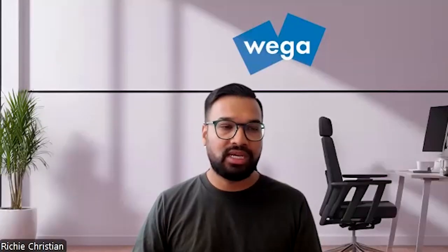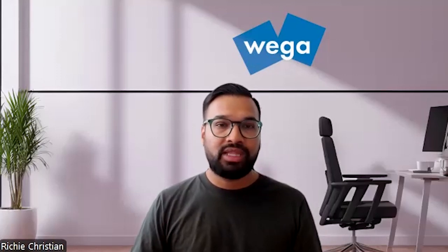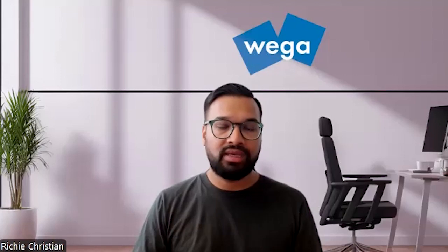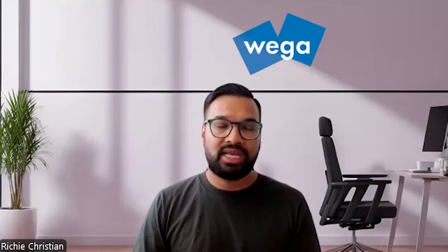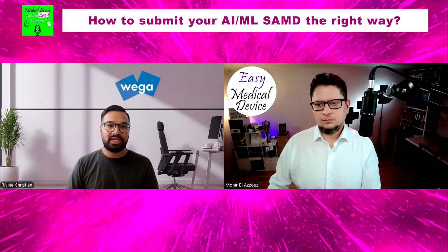I'm not aware of any medical device specific validation standards in this context. Recently, I was at a conference and I heard about a verification standard being developed for AI ML systems. So I think there's guidance around verification, but not so much around validation, specifically in the med device setting. So this is really where companies have to get their cross-functional teams together and really look at their specific device and its intended use and understand what is the reference standard. It could be, if you're going through a 510(k) pathway, you already have a predicate device which has used a reference standard, and that already gives you some thoughts around what your reference standard could be. But in terms of standards currently available, I'm not aware of any.